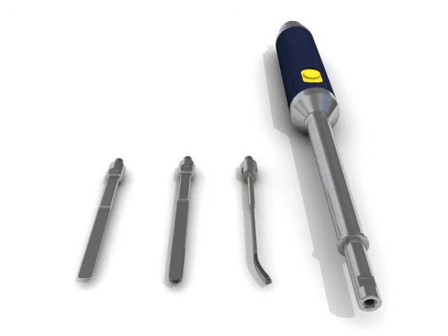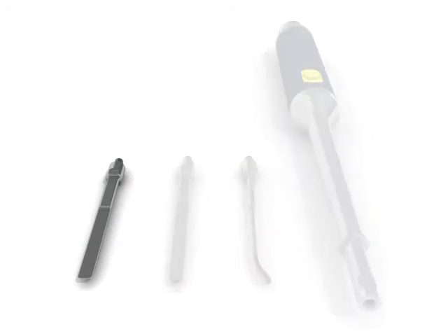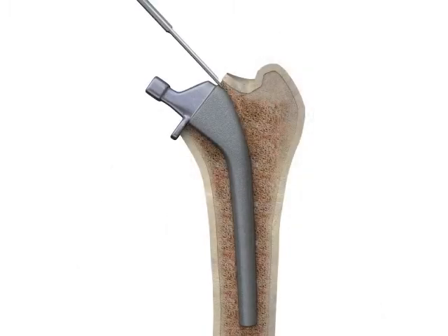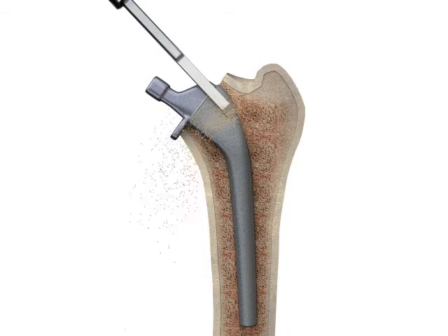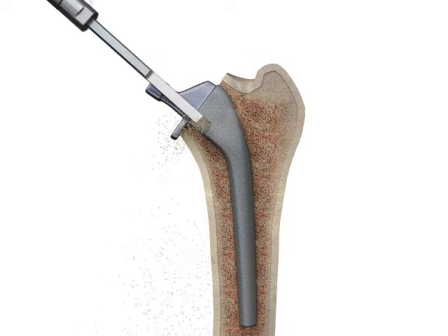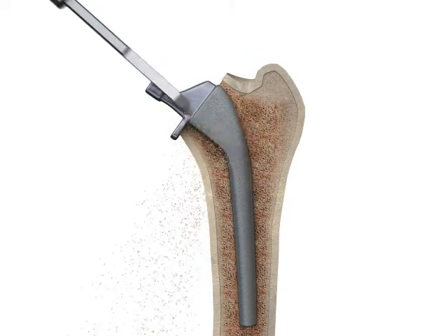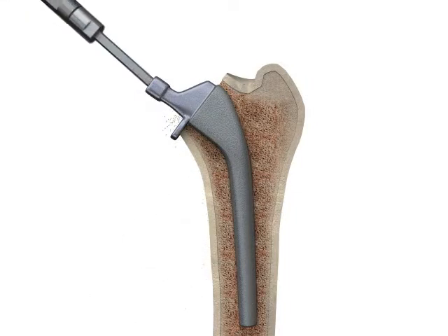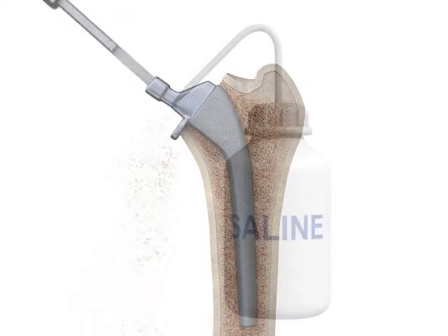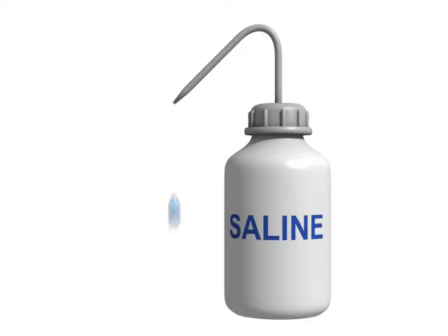The flat osteotome probes are used in the removal of proximally coated prosthetic stems. The flat 6 mm osteotome probe is first used to create slots around the stem. This is done by activating and advancing the probe down the canal next to the stem. Again, it is imperative to use saline irrigation while the probe is in use.